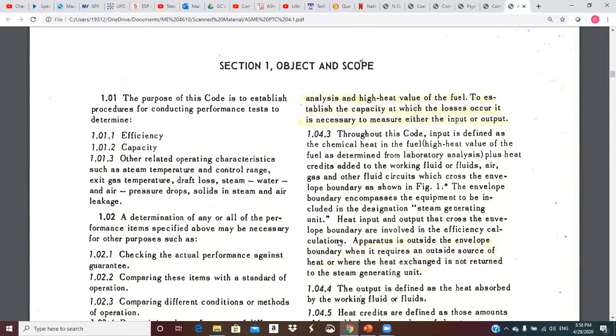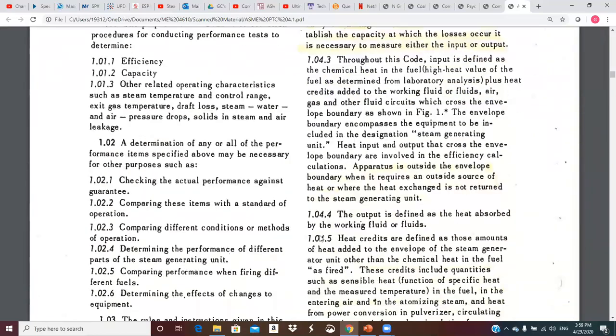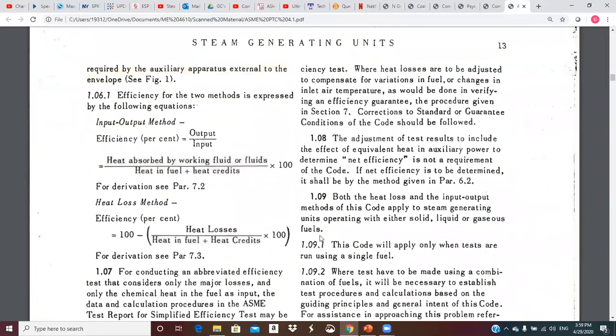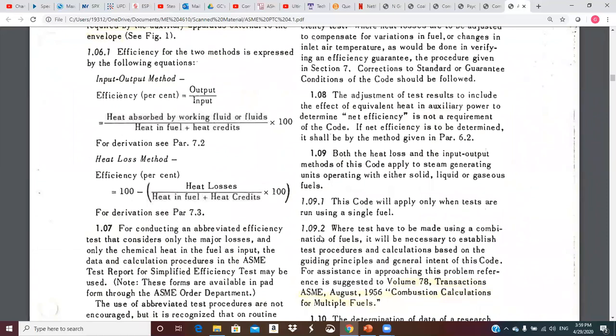If you do your own test by your own procedures and it ever gets into a court of law or legal proceeding, they're going to challenge that. Say, well, that's not the right way to do this. Well, this is the document that lays out the appropriate way to do a test so that everyone should be able to be on the same page. Other related operating characteristics such as steam temperature and control range, exit gas temperature, draft loss, steam, water, air, pressure drops, solids in steam, and air leakage.